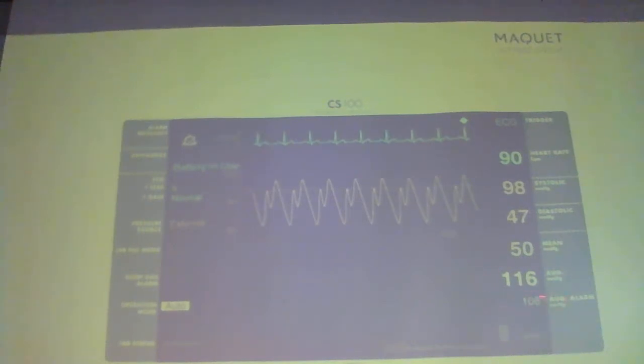Unlike your monitors where you have a systolic blood pressure alarm, this goes off an augmented pressure alarm, because that's what we're really trying to maximize with this pump: the augmentation. So you'll see that the augmentation alarm is set to here. It calculates over a 3-minute average what the average diastolic augmentation pressure is, and it reduces 10 millimeters of mercury. So it's basically saying, hey, we've averaged 116 for 3 minutes, your alarm's going to be 106. And you can adjust that if you need to. But in the unit, we always set it about 10 to 20 below.